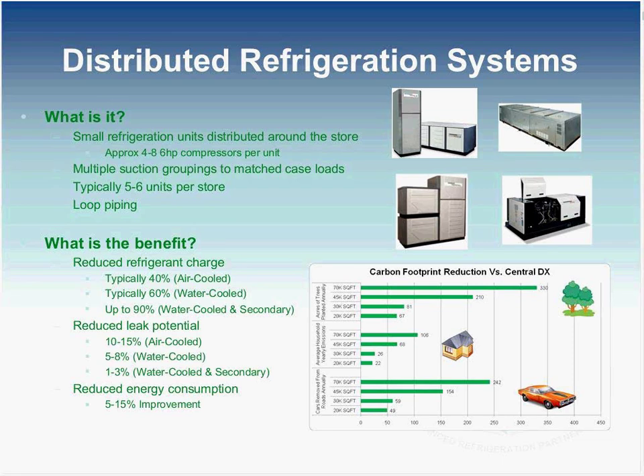Compared to an air-cooled system, a distributed system typically reduces a refrigerant charge in the neighborhood of around 40%. And again, it does depend on what type of centralized system you're comparing it to. If you're comparing against a loop system, the charge reduction would vary. When you look at a water-cooled system, water-cooled would be the means of condensing the refrigerant versus the traditionally used air-cooled condenser. We see charge reductions in the neighborhood of 60%. And when you combine a distributed-type refrigeration system in a secondary format, like a glycol system, in conjunction with a water-cooled condenser, you can see charge reductions up to 90%. Compared to a traditional DX system.